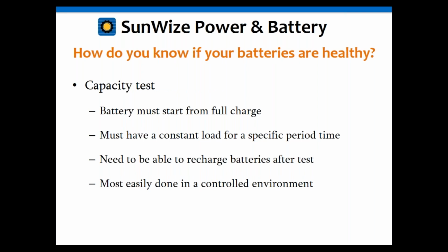If you want more information on capacity tests, most battery manufacturers have details on those as well, by the way. So if you contact the battery manufacturer or us, contact SunWize with the batteries you have, and we'd be happy to get you the capacity test recommended by the manufacturer on that.